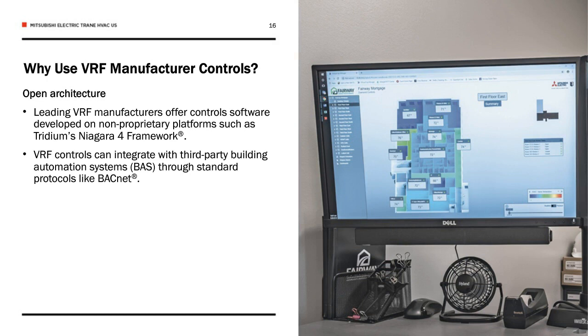You could do a 4-hour presentation on this topic, but I'll try to be brief here. When you have a heat pump system, and I think the question was based on a heat pump system or a non-simultaneous VRF system that does not have the ability to simultaneously heat and cool from the same refrigerant circuit, there's a few options. One of them is to just strictly schedule the unit. You can schedule the unit to say we are in heating at this time of the year, we are in cooling at this time of the year. This sets expectations and allows the occupant to know what they're getting at this time of the year, and a manual button push, if you will, has to be done in order to change it on a unique day. A day in May where it's incredibly cold, or a day towards the end of the springtime where it just becomes incredibly warm and you need cooling.